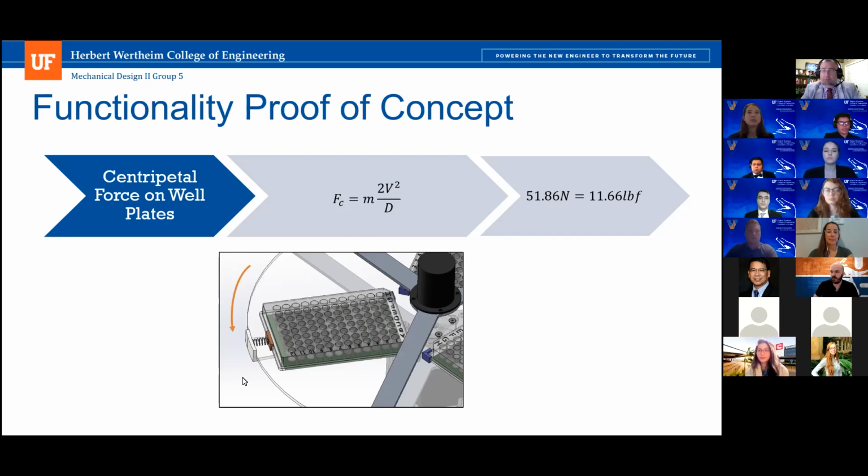It's good that you specify that, because the actual maximum length required by customer needs was 72 inches. So the length that we have is much smaller than that. And regardless, even if it's not fitting into a BSC, which is BSL2 required, the inside of the chambers are sealed and controlled via those air check valves, so that the environment in there will not interact with the environment outside at all, not until it passes through the laboratory HVAC system.